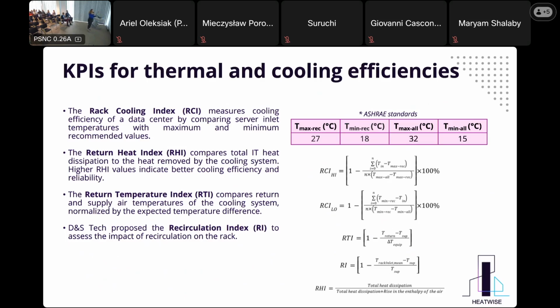The return heat index compares total IT heat dissipation to the heat removed by the cooling system. Higher RHI values indicate better cooling efficiency and reliability. The return temperature index compares return and supply air temperatures of the cooling system, and it can be calculated with this formula. The closer the value is to 1, the higher the efficiency of the system, which means the difference between the return temperature and supply temperature is very low, maybe almost 0. But this is not very possible in real life because there are heat dissipation, friction, and other dissipation mechanisms. So as close as possible to 1 is our desired target value.